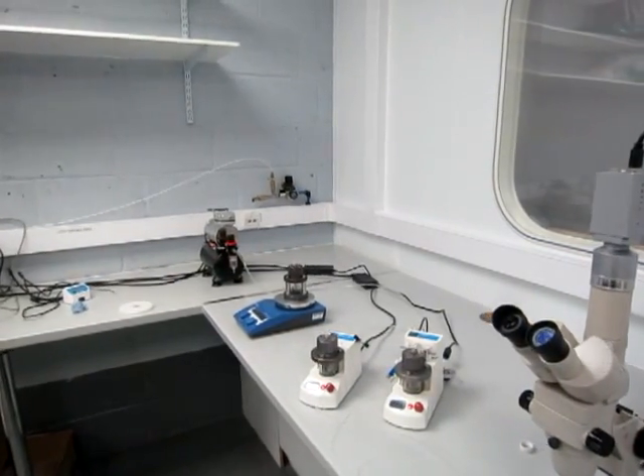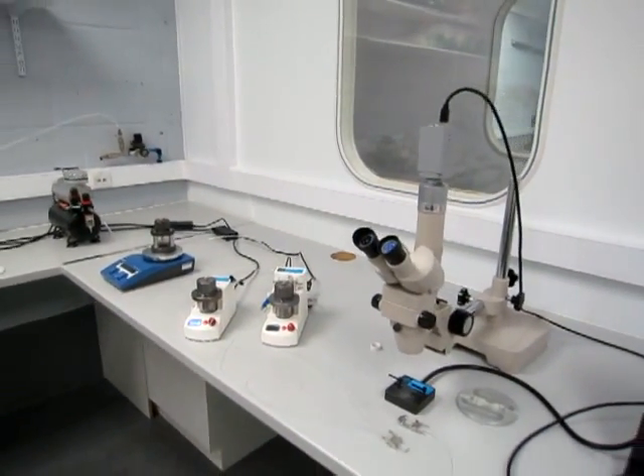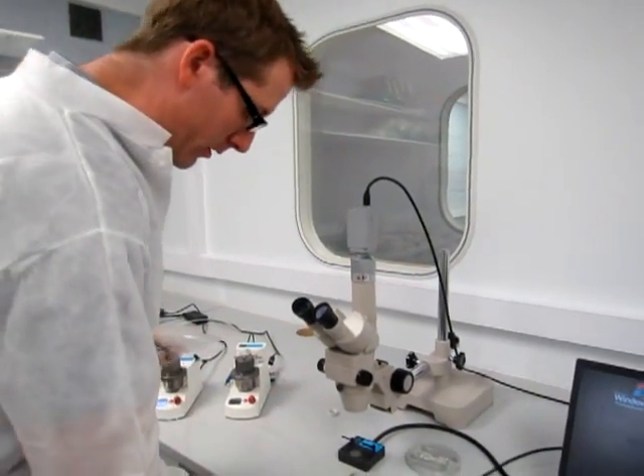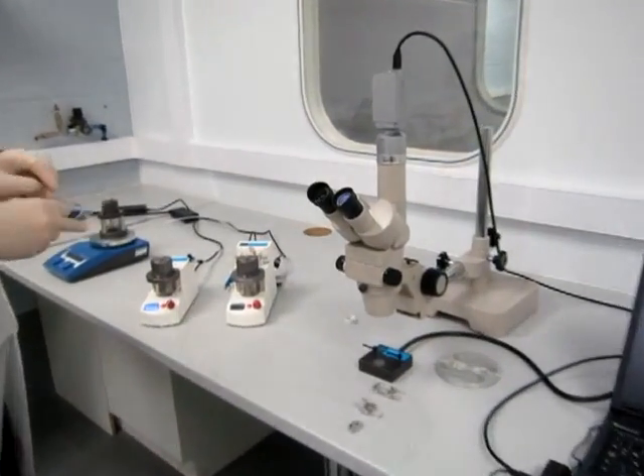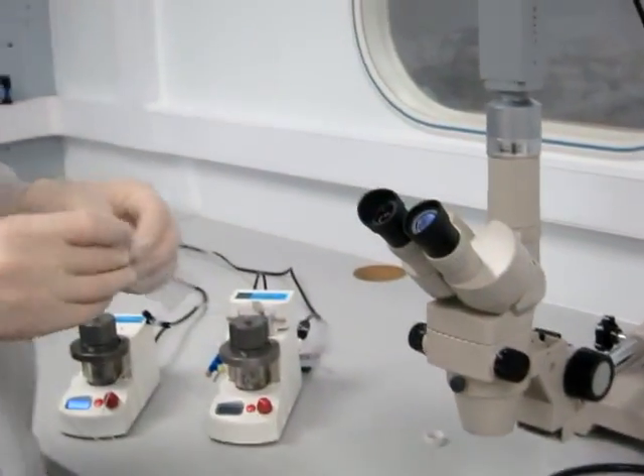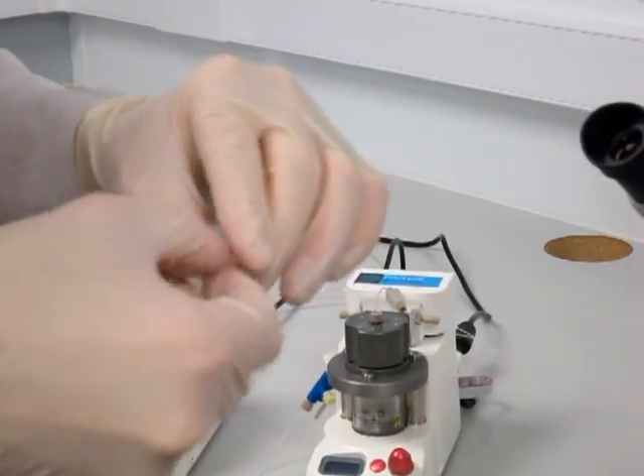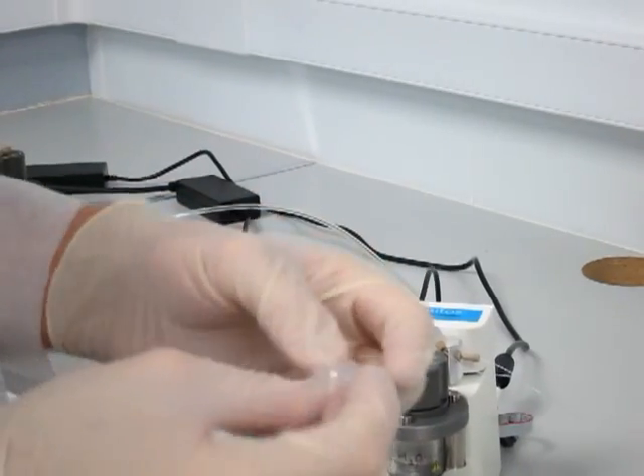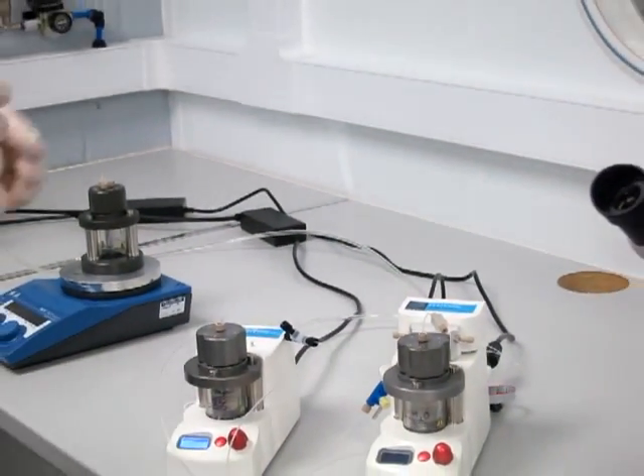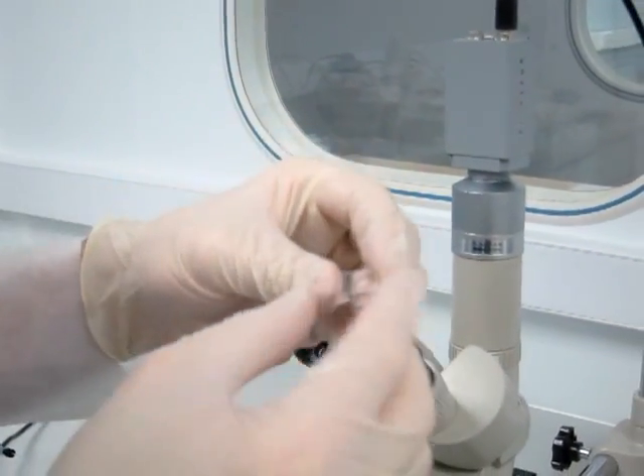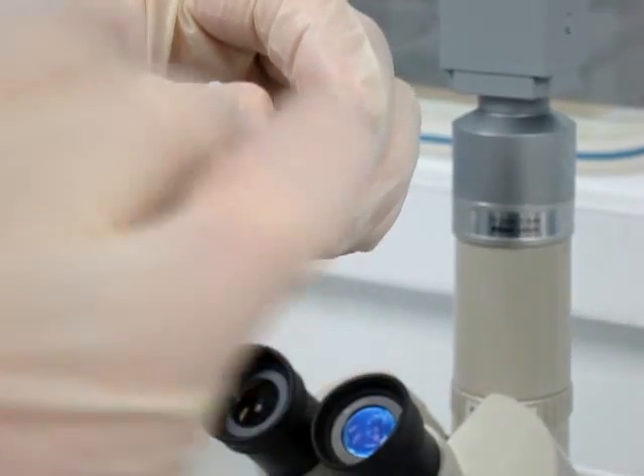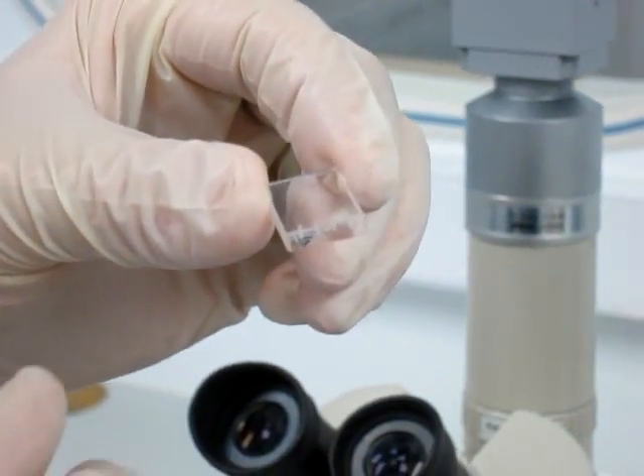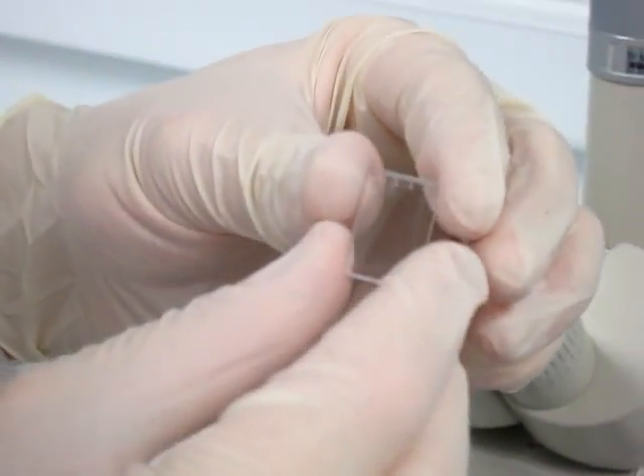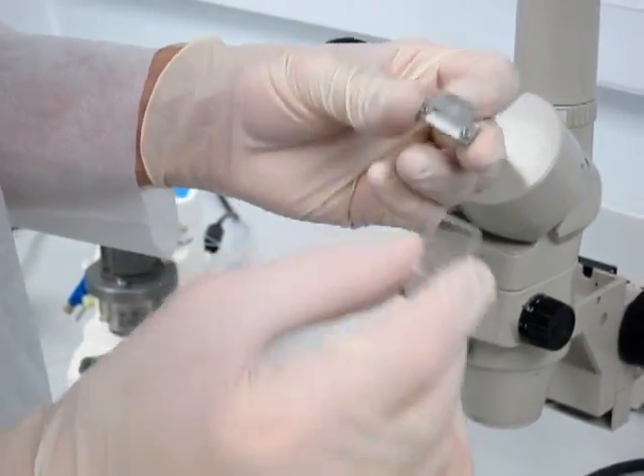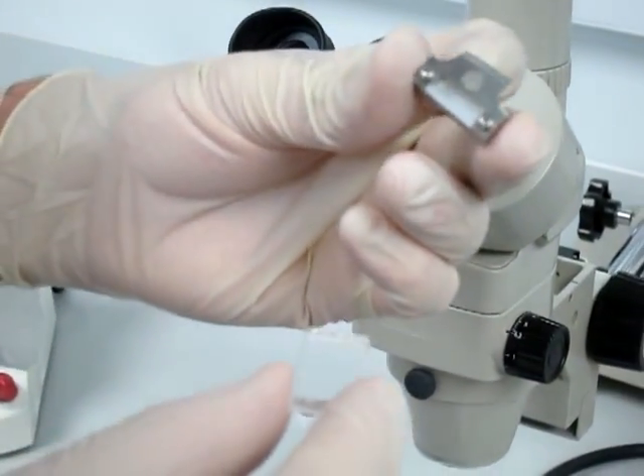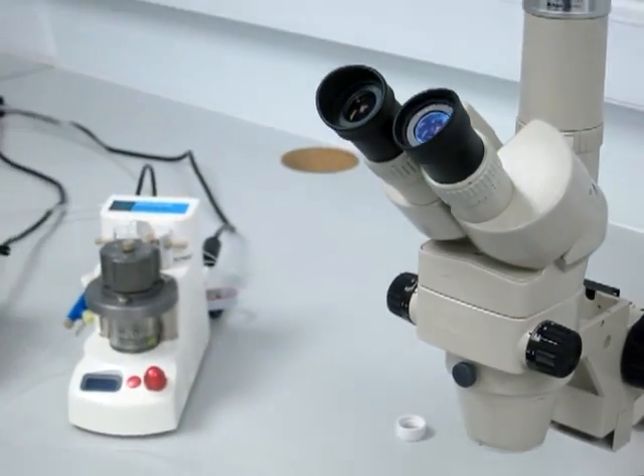There's one other type of droplet chip. This is a small droplet chip. These smaller droplet chips are for running droplets in the range going below 30 microns down to about 2 microns. Rather than having holes coming in the side, because the channels are quite a lot smaller, we have to use the top-down holes. This chip has channels which are about 5 microns deep, but there's also a version which is about 14 microns deep. So this chip goes into a top-down interface. I think it's slightly damaged.